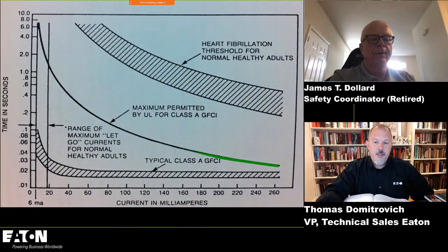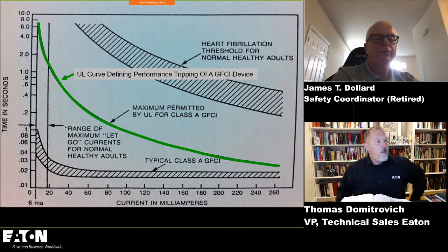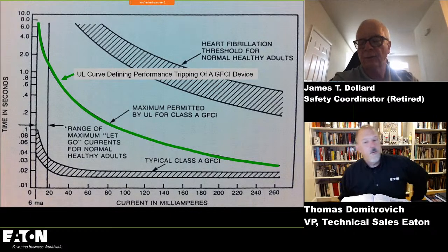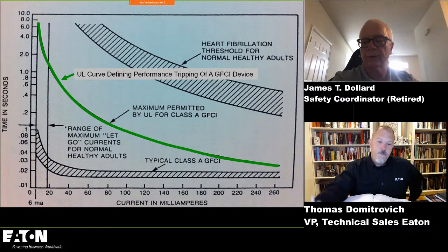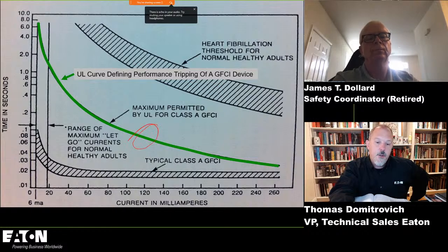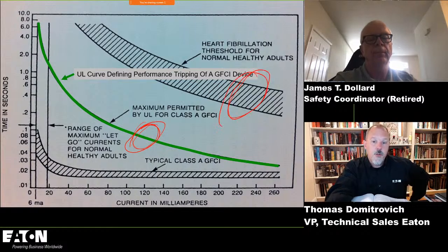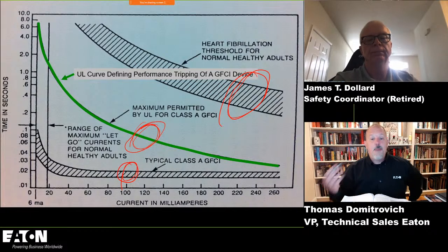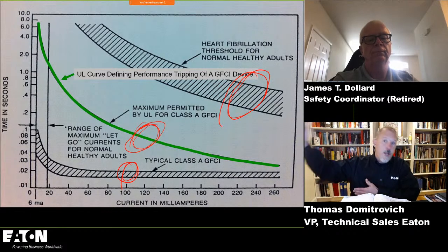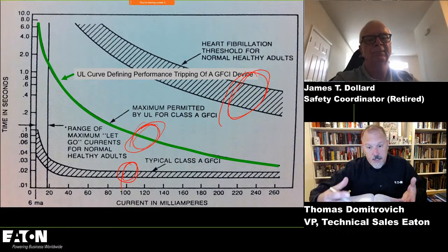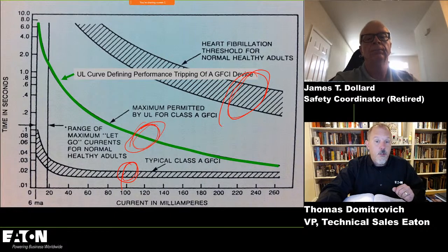They wanted to control the path through the body. It's the path, the magnitude, and the time. They're the three things that are going to determine the outcome of a shock incident. And this is your magnitude. This is what UL tells you the threshold needs to be. This is the threshold from the perspective of your heart going into fibrillation, and this is actually where your Class A GFCIs operate and function, which is much faster than where the UL threshold is, just because of the physical nature of the devices, and much faster than your heart going into fib.